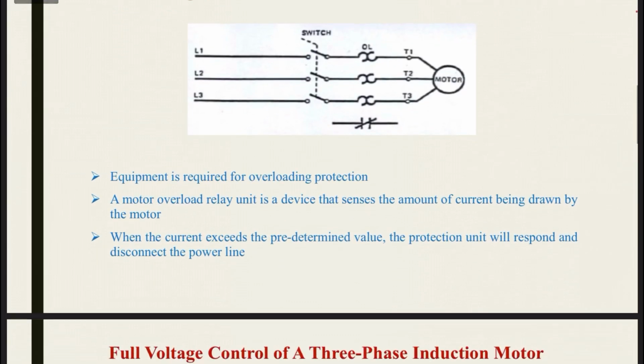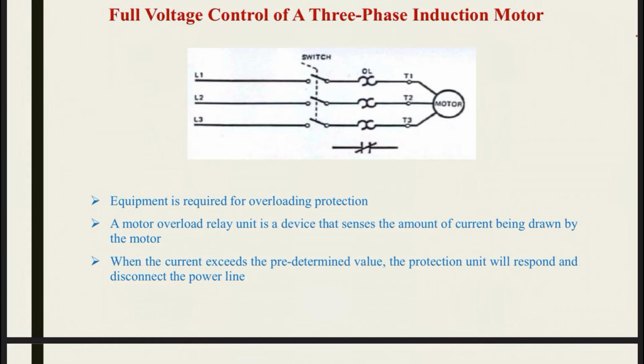Next graph here we have. Equipment is required for overload protection. This is OL, the overload relay for protecting the motor. A motor overload relay unit is a device that senses the amount of current being drawn by the motor. When the current exceeds the predetermined value, the protection unit will respond and disconnect the power line. This is the function of the overload relay: when the current is high, it disconnects the power line to protect the motor.